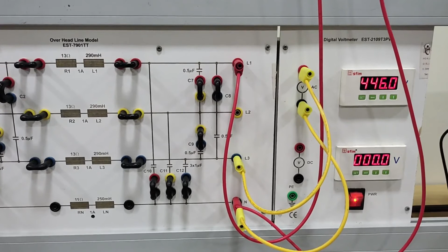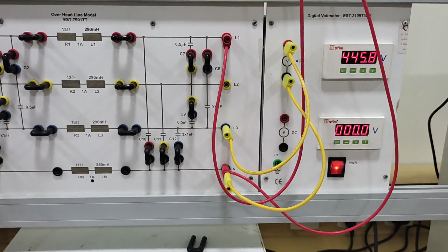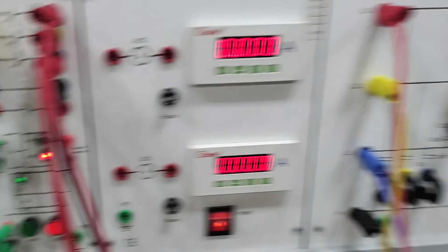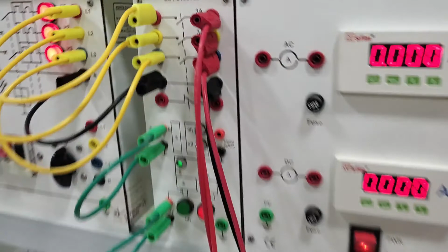Next students, we can see that for phase 1, that is L1, we can measure the voltage, and as you know that L1 is short circuited with the earth, so you will see that voltage will be 0 for L1 phase. So next we will remove this L3 wire and we will connect it towards L1, and then we will see what will be the voltage for L1, whether it should be 0 or not. So again we will switch off our circuit breaker from here, and we will connect the L3 point to L1, and again we will switch on our circuit breaker, and you will see here that we have a short circuit current, but as the first phase is short circuited, therefore its voltage is 0 volts. You can see here that it is 0 volt. Okay students.